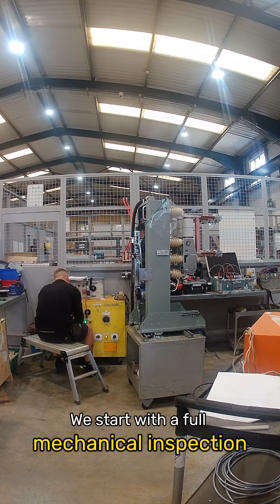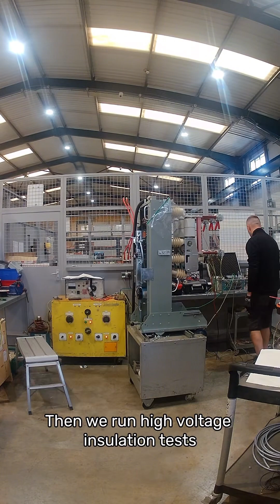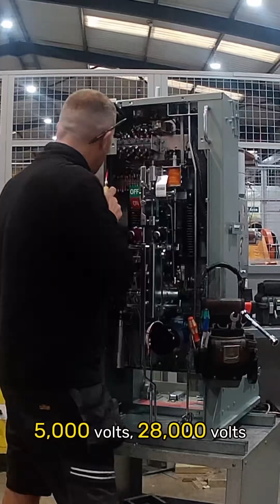We start with a full mechanical inspection, checking every nut, bolt and split pin. Then we run high voltage insulation tests: 5,000 volts, 28,000 volts, and then another 5,000 to make sure there's no electrical leakage.